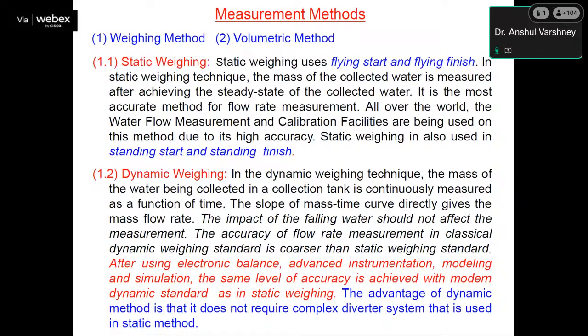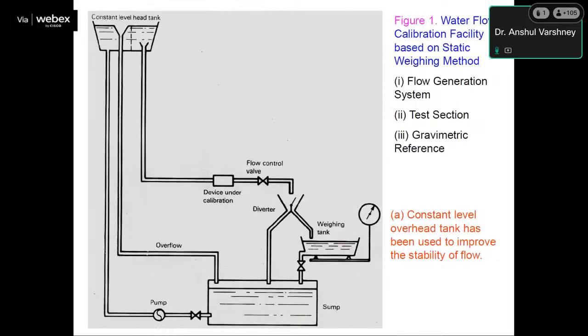However, in the dynamic weighing method, the mass of water being collected in a collection tank is continuously measured as a function of time. The slope of that mass-time curve will directly give you the mass flow rate. But the accuracy of dynamic weighing is not as good as static weighing.